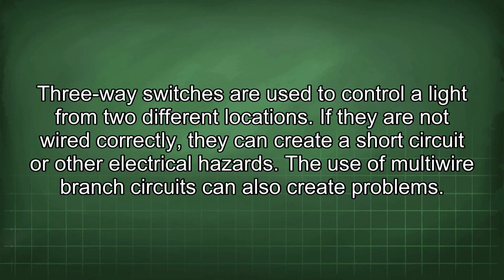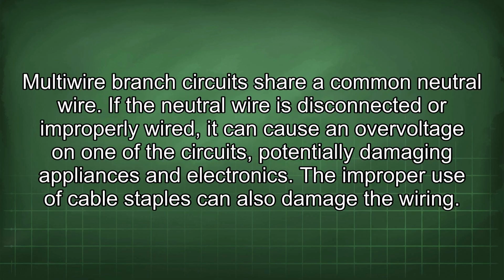The use of multi-wire branch circuits can also create problems. Multi-wire branch circuits share a common neutral wire. If the neutral wire is disconnected or improperly wired, it can cause an overvoltage on one of the circuits, potentially damaging appliances and electronics. The improper use of cable staples can also damage the wiring.